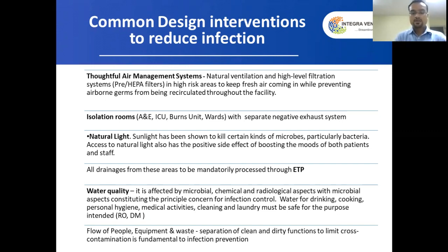We need to take care of the filtration level of the air and have the proper pressure gradient. In infectious areas, we need negative pressure in relation to other areas so infection doesn't travel out. There needs to be separate, dedicated exhaust areas in these isolation rooms.